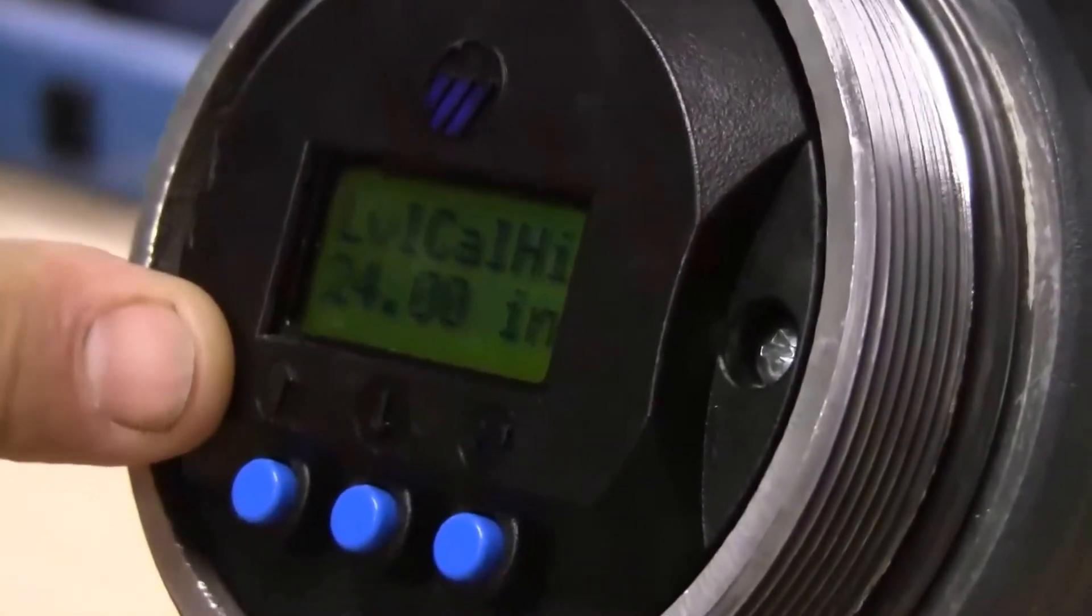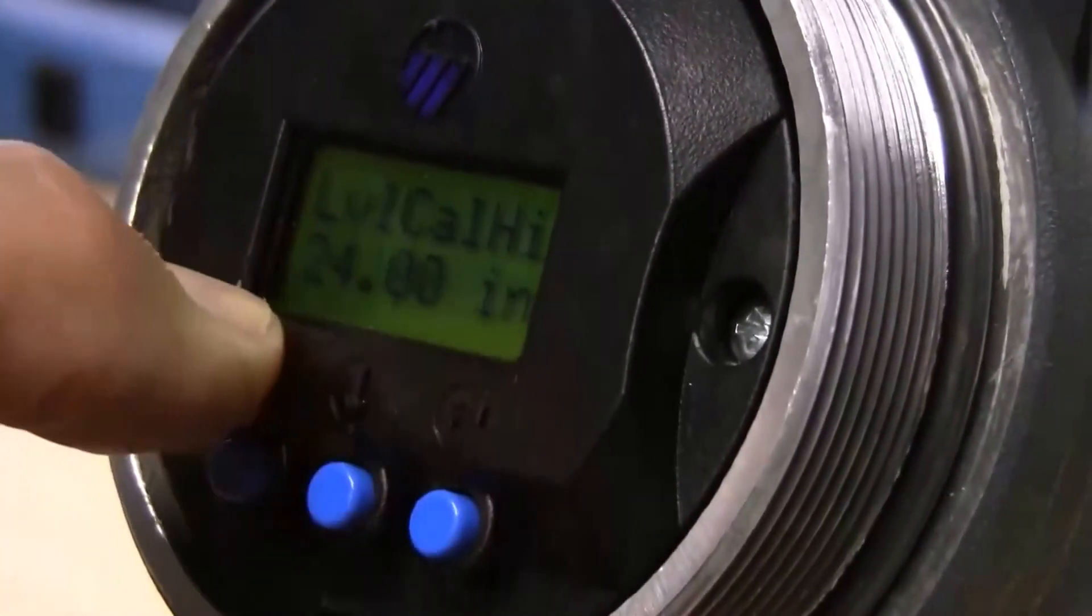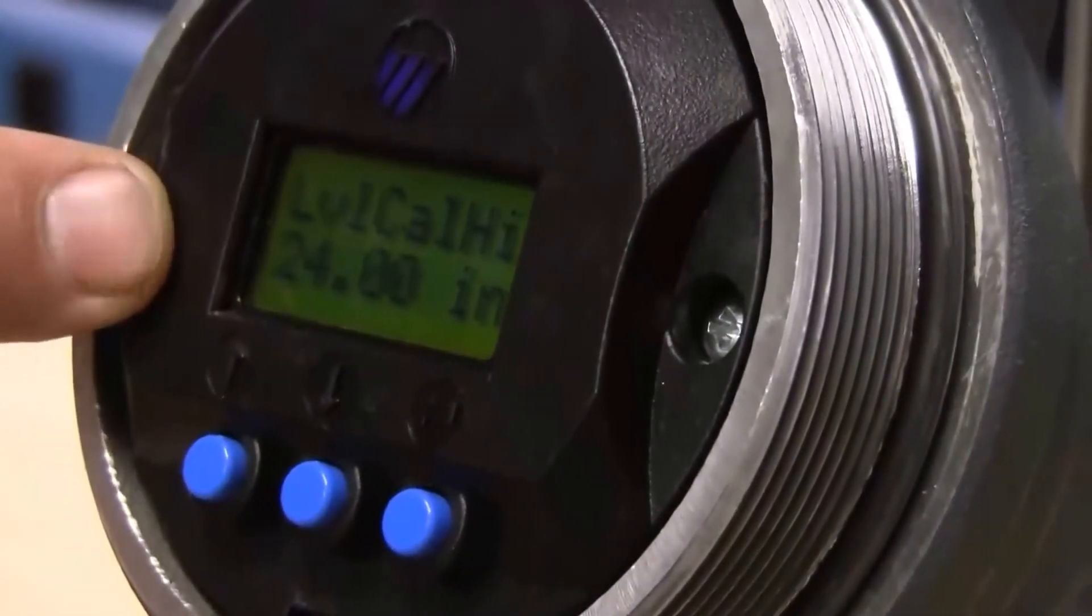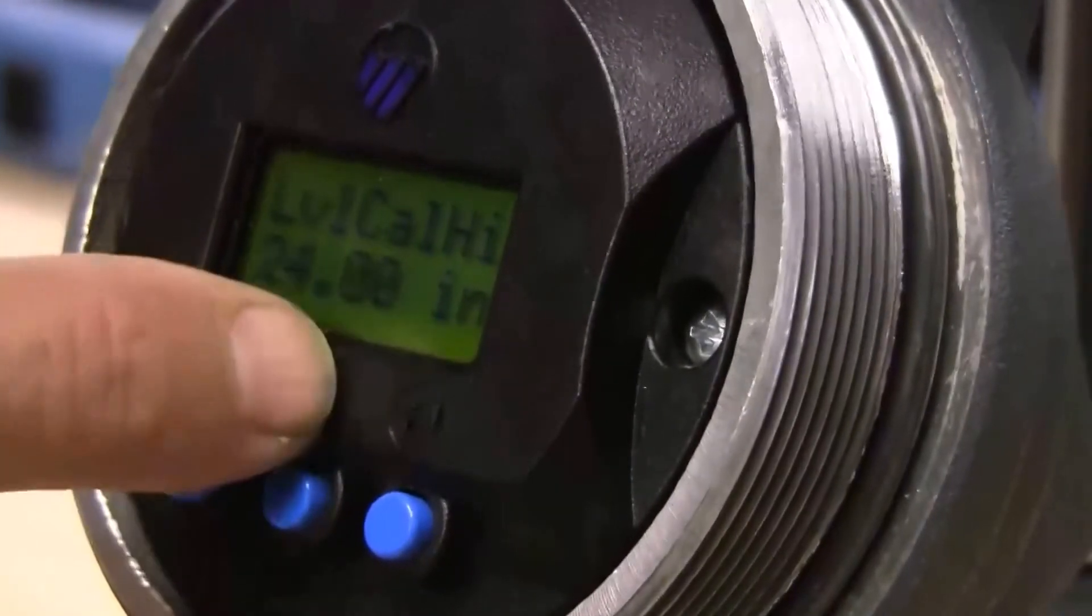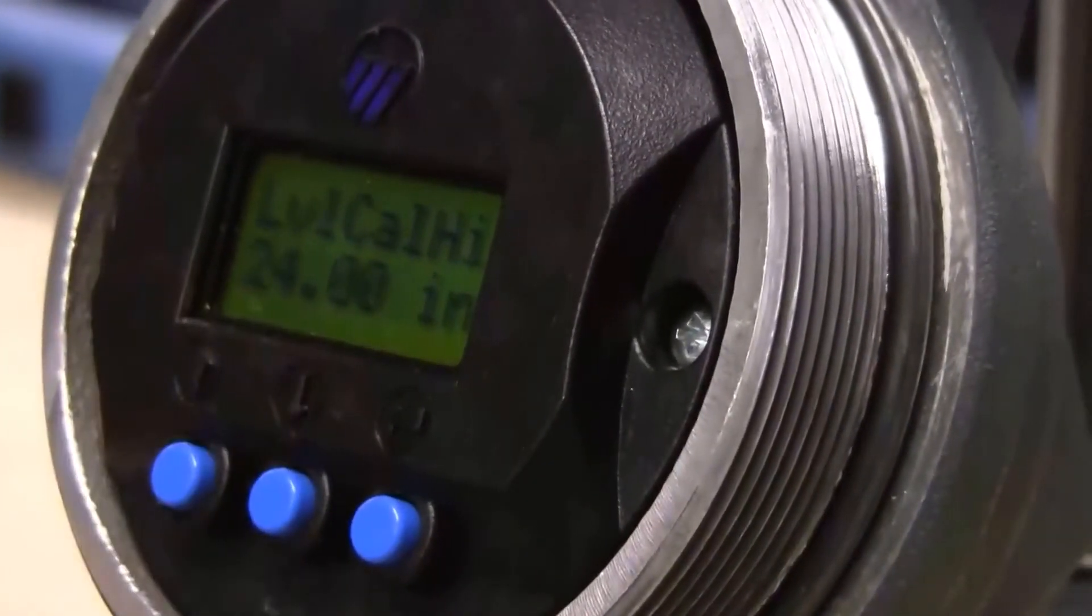Now the level cal high, if this was a 48 inch displacer, the 24 inches is appropriate for a 50 percent level. If I had 75 percent level on a 48 inch displacer, that would be a 36 inch level. If I had 100 percent on the 48 inch displacer, that would be a 48 inch reading that I would want to see. So we're going to keep this at 24 inches.